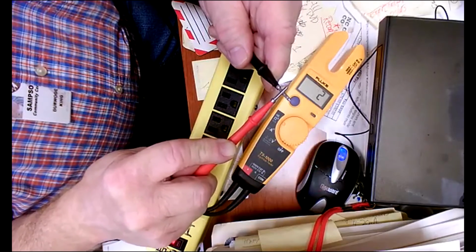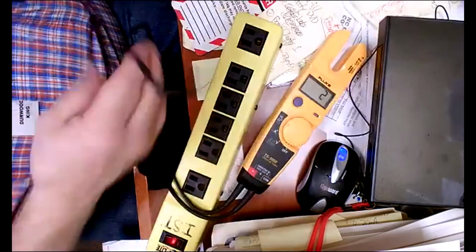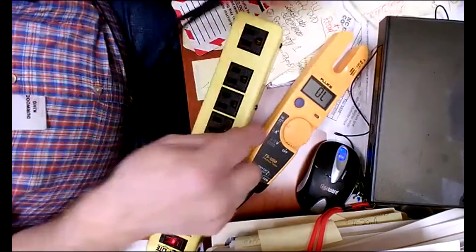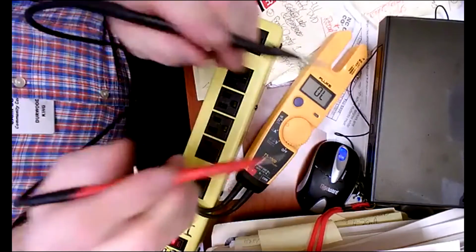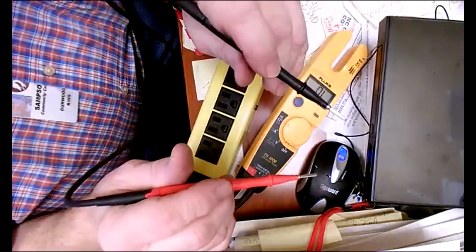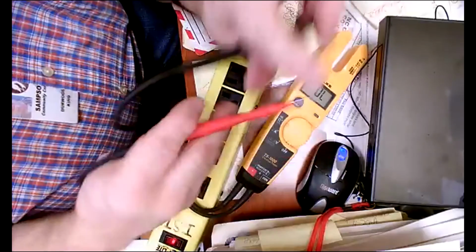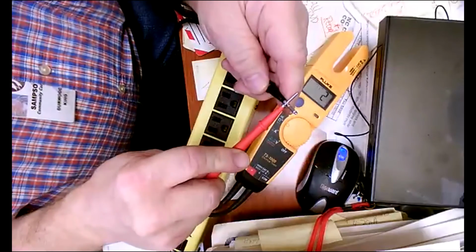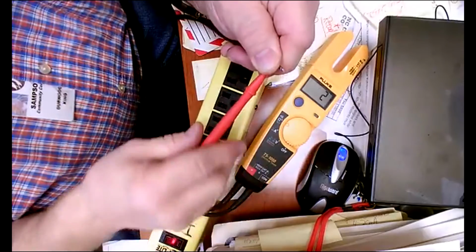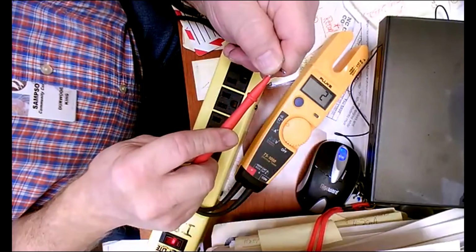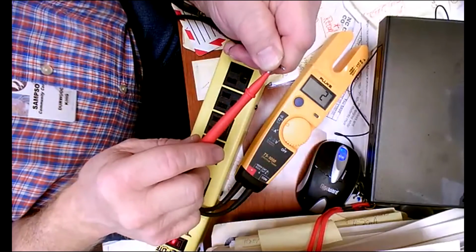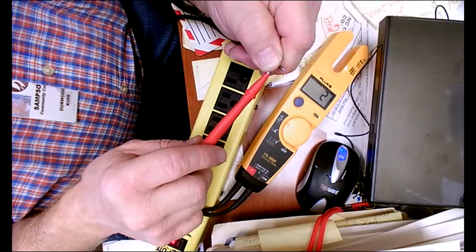So if you have a 2 right here, just in the travel of the test leads, 2 ohms of resistance, and then you go across the heater element and you get, say, 16 ohms. You would say 16 minus 2, and it would give you a real resistance of 14 ohms for the heater element. Okay? Does that make sense?